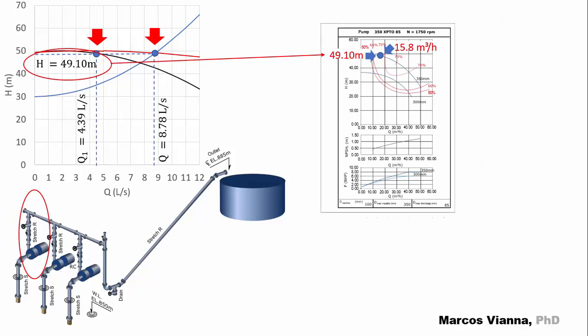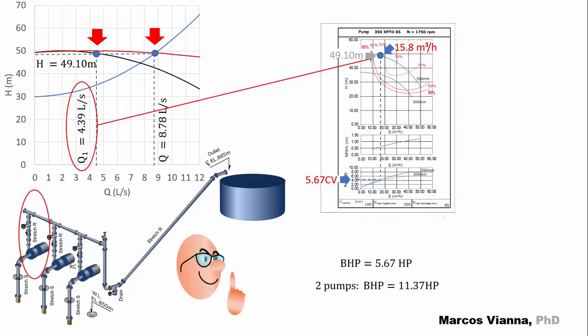Here is the operating point in the pump chart, the flow and the manometric head. From this point, we can find the power of each point. Notice that the power of the installation will be twice the power of each pump. We can find the NPSHR and the efficiency too.